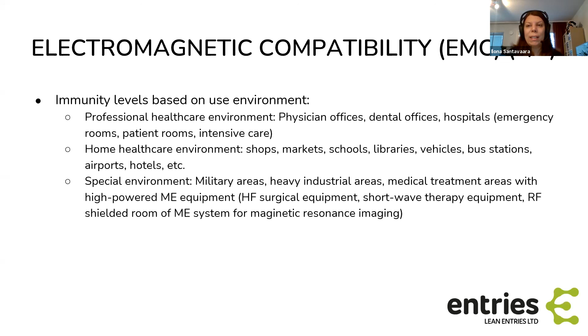So if you have multiple different pieces of equipment, or even an adapter and a piece of equipment, it's sometimes not very easy to get those compatible for the requirements. So it's not a plus minus calculation when you're taking into account multiple different equipment. It can sometimes be quite surprising, but you should really do pre-testing and be quite mindful of this. So it's not one of those parts of the standards where it's mostly just testing. It needs expertise to do this.